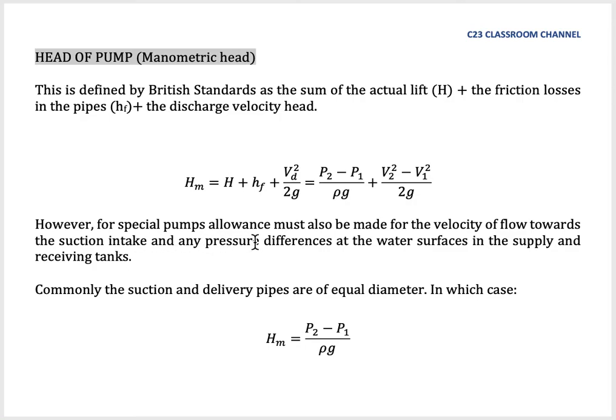However, for special pumps, allowance must also be made for the velocity of flow towards the suction intake and any pressure differences at the water surfaces in the supply and receiving tanks. Commonly, the suction and delivery pipes are of equal diameter. In this case, we could simplify that because the suction and delivery pipe, if the diameter is equal, means the velocity remains constant. It remains the same in inlet and outlet here. The value here will become zero. We could say that the manometric head here is only equal to the pressure drop, P2 minus P1, pressure at outlet minus pressure at inlet, divided by rho g.